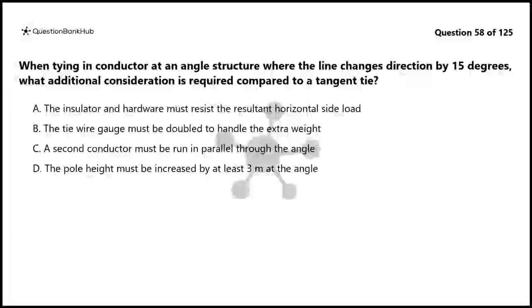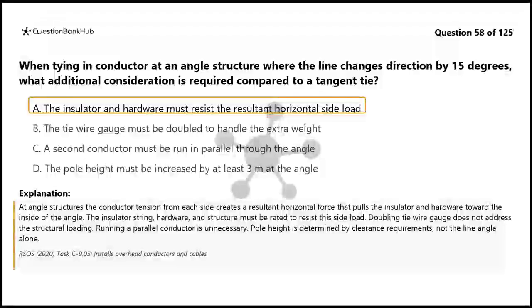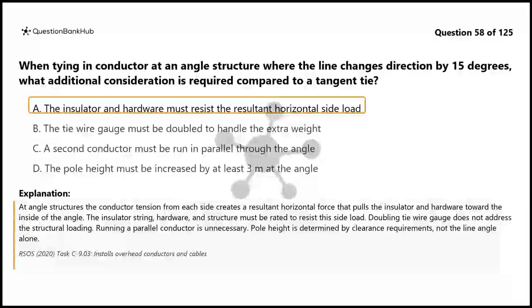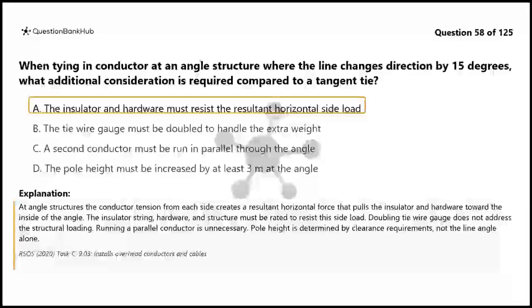The correct answer is A. At angle structures, the conductor tension from each side creates a resultant horizontal force that pulls the insulator and hardware toward the inside of the angle. The insulator string, hardware, and structure must be rated to resist this side load. Doubling tie wire gauge does not address the structural loading. Running a parallel conductor is unnecessary. Pole height is determined by clearance requirements, not the line angle alone.